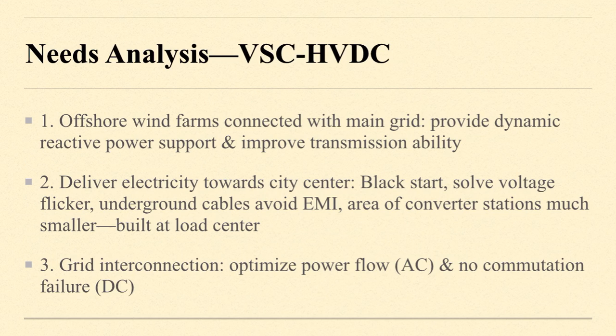And next is VSC HVDC. It has many functions. It can connect offshore wind farms with the main grid to provide dynamic reactive power support and improve the low voltage ride through ability of wind farms. Next, it can deliver electricity to load centers in cities, with many advantages including black start and resolving voltage flicker; underground cables can avoid EMI, and the area of converter stations is much smaller. And the third is grid interconnection. Compared with AC, it can optimize power flow, and for DC, there is no commutation failure.